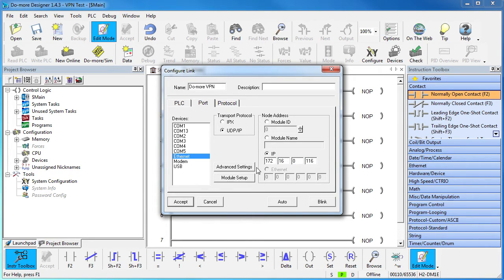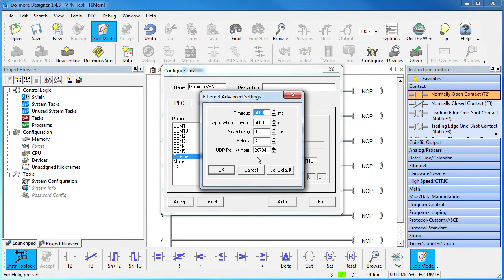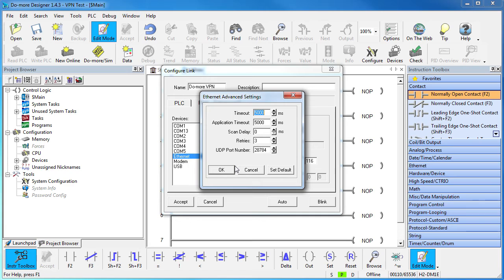And while we are here, let's make sure the default Do-more port number is correct. This 28784, that's perfect. When using a VPN, this always needs to be this number, which is the listening port on the Do-more, assuming you are using the primary Ethernet port.